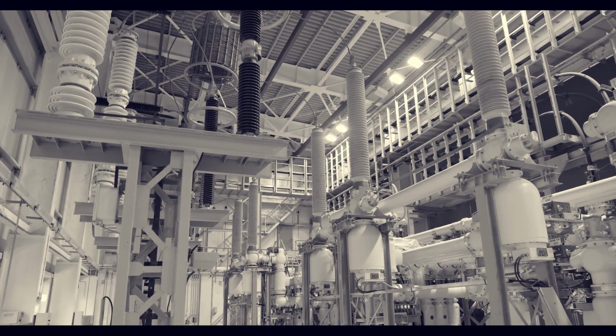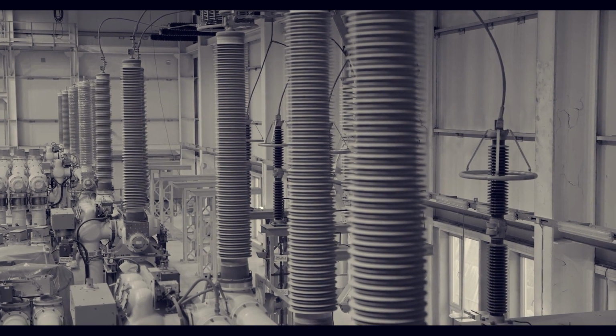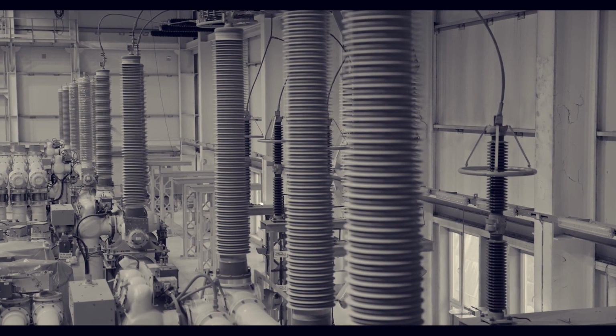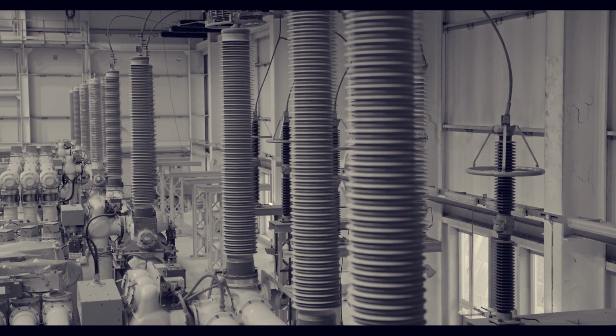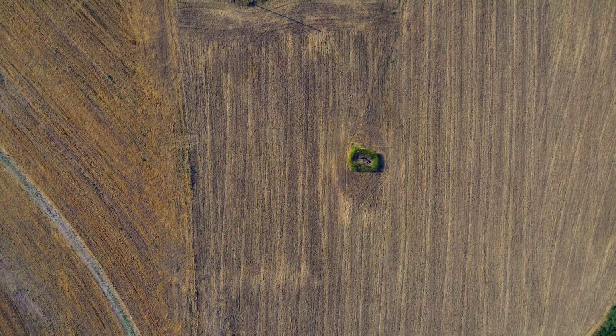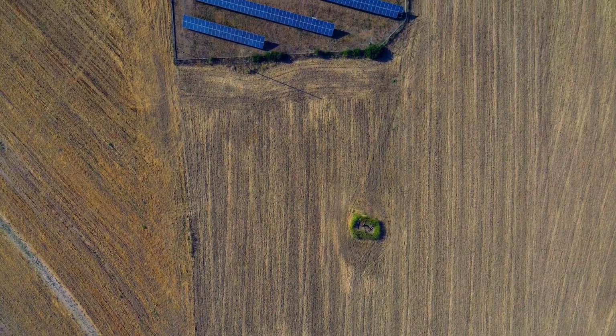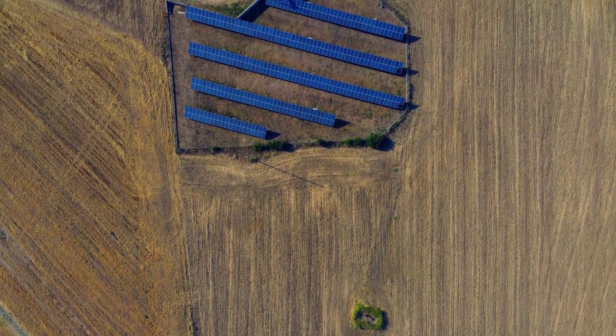Here's the loop. Every gas turbine retiring right now is taking something with it. Not just megawatts. Megawatts are replaceable. Solar and wind generate megawatts at scale. What's harder to replace is the physics. The inertia stored in spinning metal. The fault current that makes protection relays operate in under a second. The reactive power that stabilizes voltage automatically as conditions change. These weren't services anyone formally designed and paid for. They were side effects of machines built to do something else. And now that the machines are going away, we're finding out what those side effects were actually worth.